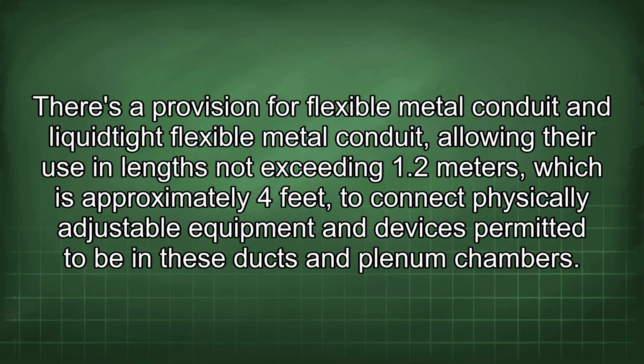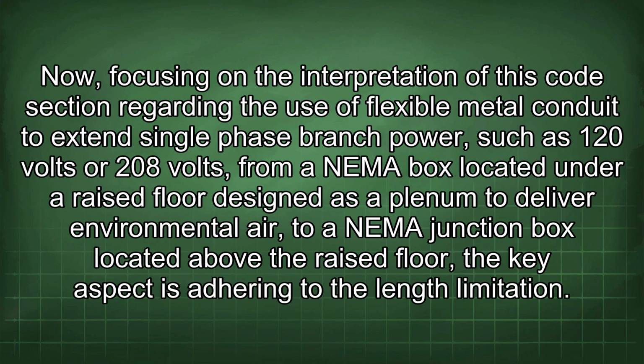There's a provision for flexible metal conduit and liquidtight flexible metal conduit, allowing their use in lengths not exceeding 1.2 meters, which is approximately 4 feet, to connect physically adjustable equipment and devices permitted to be in these ducts and plenum chambers. Now, focusing on the interpretation of this code section regarding the use of flexible metal conduit to extend single-phase branch power, such as 120 volts or 208 volts, from a NEMA box located under a raised floor designed as a plenum to deliver environmental air to a NEMA junction box located above the raised floor.